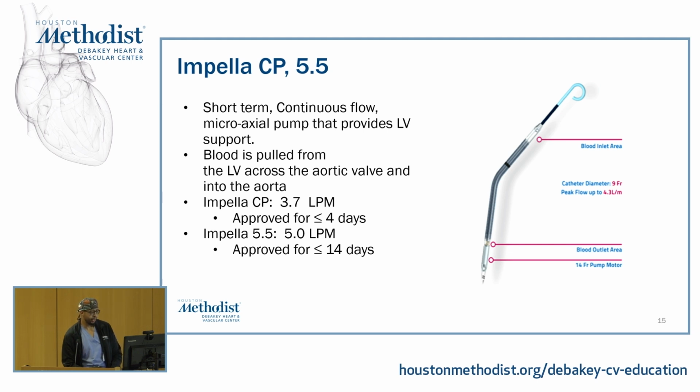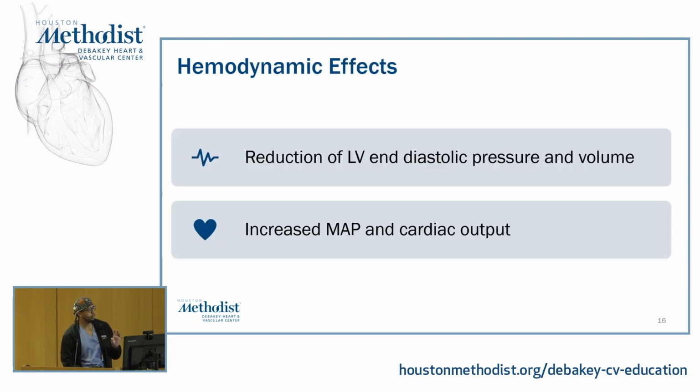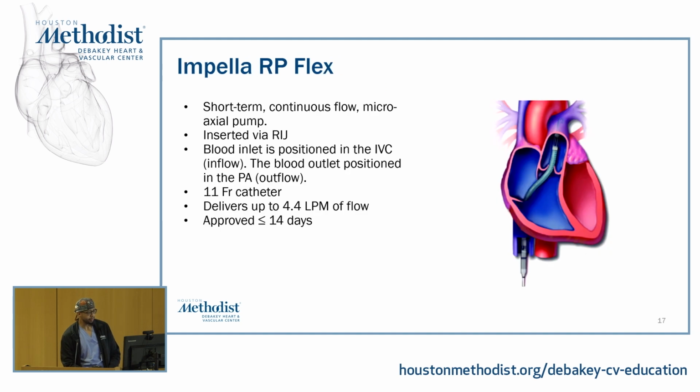The Impella CP is approved for up to 4 days. The Impella 5.5 is approved up to 14 days. When you go beyond those limits, you're going to start having mechanical failures, so you're going to start losing the internal sensors that are built into them, no longer seeing the waveforms that you would normally see on your monitor, which I'll show you in just a moment. In regards to the hemodynamic effects, the Impella reduces LV end-diastolic pressure and volume, as well as increases your MAP and cardiac output.